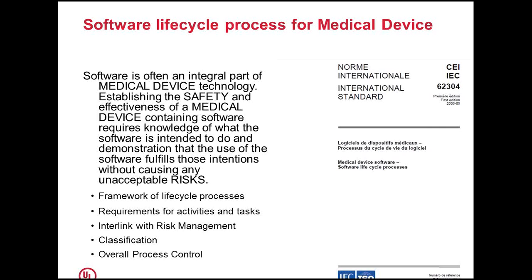IEC 62304 gives a framework for the life cycle process. It specifies requirements for what activities and tasks are to be performed while developing the software, its interlinks with risk management, requirements for classification, and requirements for overall control of the process. We are going to discuss all these things in the coming slides.